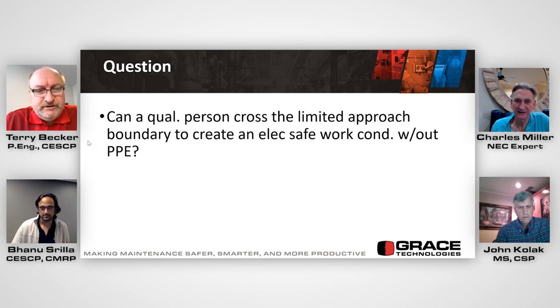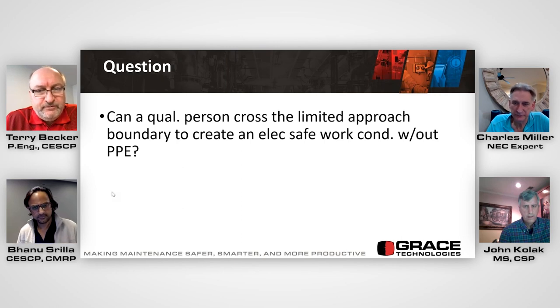I think these boundaries are mixed up in this question. You can't cross the restricted approach boundary without shock PPE. And if you're inside the arc flash boundary and going to be at the working distance, you need arc flash PPE on, equal to or greater than the incident energy on the label, or as defined by converting the arc flash PPE category to a minimum arc rating of clothing.